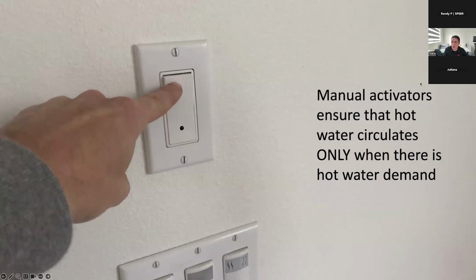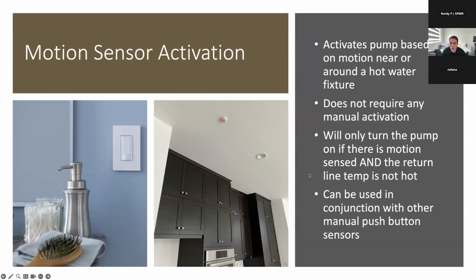Manual activation will ensure that the circulation pump only runs when there's hot water demand, versus an occupancy sensor. But occupancy sensors are a good option as well to fully automate the system. So if you don't ever want to think about it, you can just put these occupancy sensors near the point of use or near the bathrooms. And then that will ensure that the pump never turns on if nobody's up and about in the house.